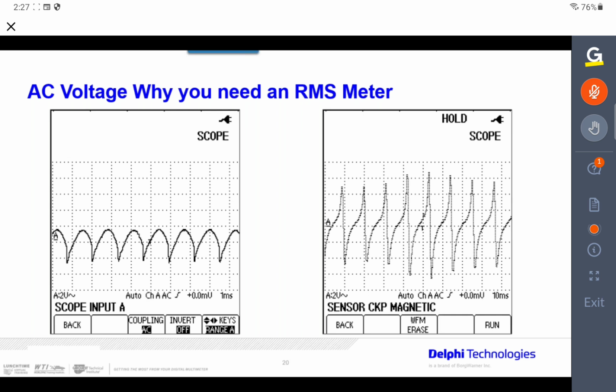It's not a true sine wave. And if it's not a true sine wave, the only way you're really going to get the information you need is to have an RMS meter to get the actual reading. So it has an algorithm, and what it goes through mathematically equivalates what it should be - equivalate's a new word, by the way. It gives you the readings you need. So again, that's why you need an RMS meter.